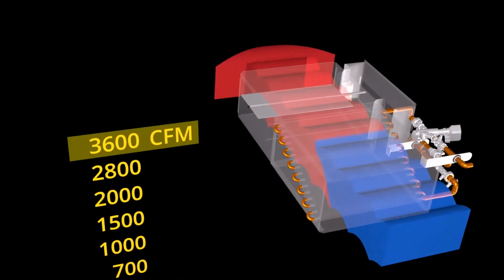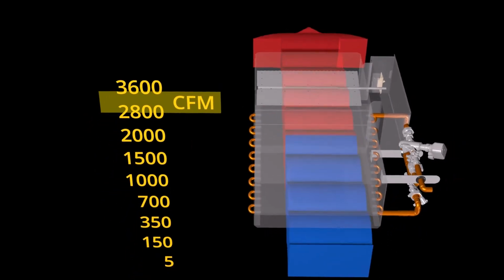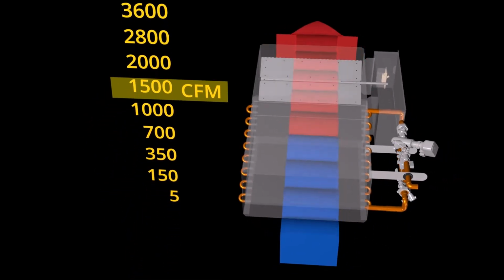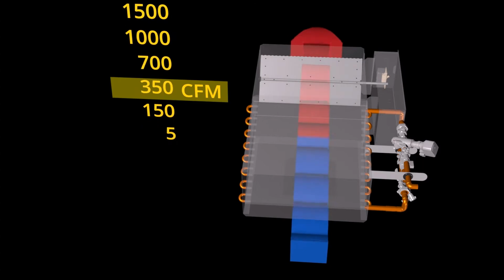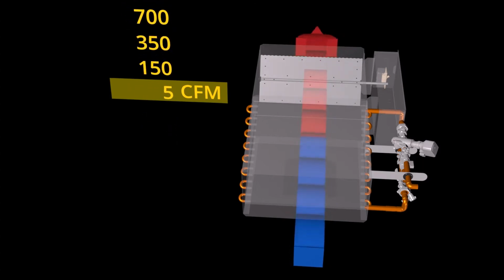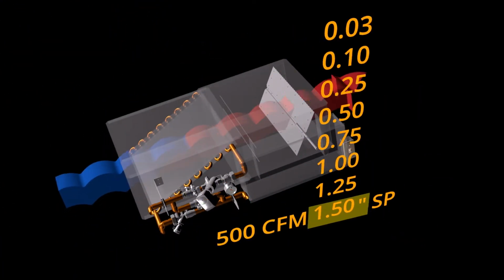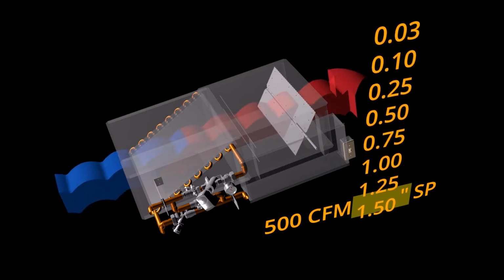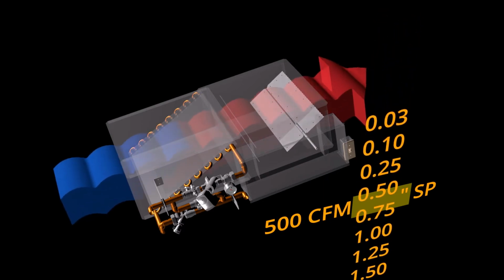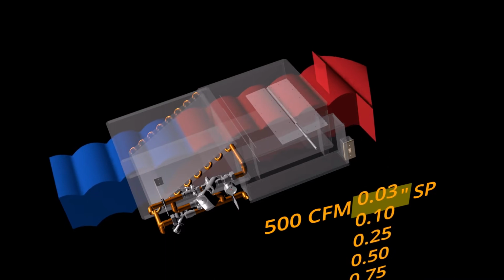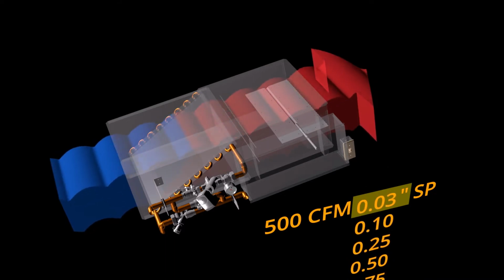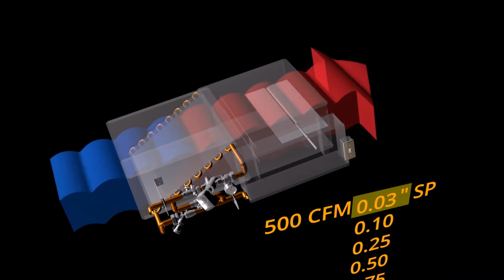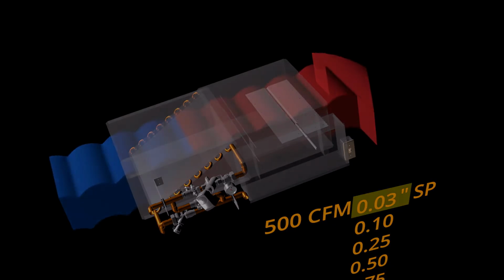With the industry-leading, disrupting turndown up to 100-to-1, the SAV can accurately control any flow, which leads to greater design and flexibility for the engineer and the building owner. Because of the patented advanced variable orifice technology, the SAV is truly pressure independent. It will meet the airflow set point and pressure without the need for field K-factor adjustments.